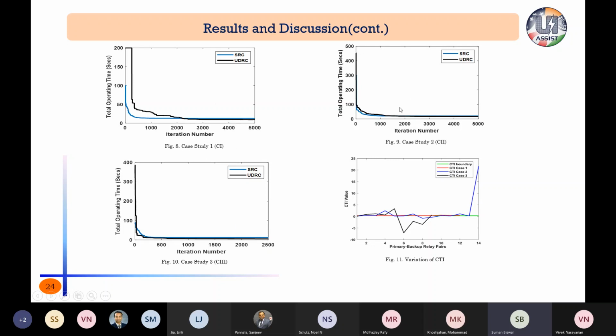So this is grid connected. This case study 2 is grid connected. Case study 3 is islanding, and this is the conventional way of operating the distribution system. And this is a graph showing that if we consider only one setting, and if we set, just for understanding, suppose this CTI boundary is 0.3 seconds, the coordination time interval criteria, that is the green line, and CTI case 1 is the distribution system operating without DG, the conventional way. So the red line signifies that if we follow that setting, then the coordination will hold definitely.